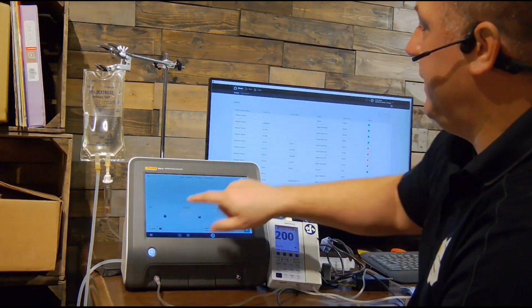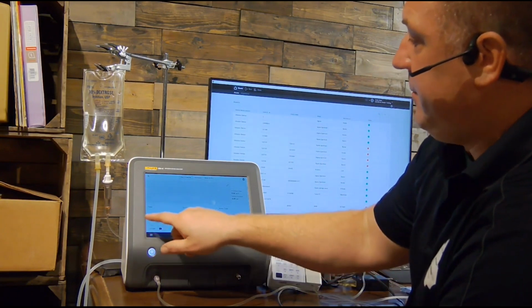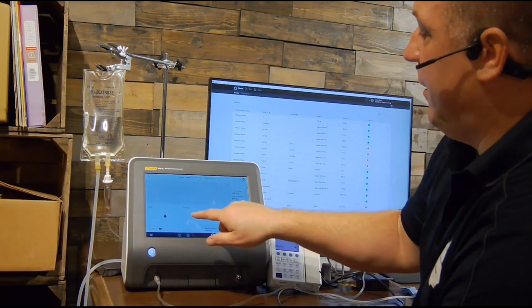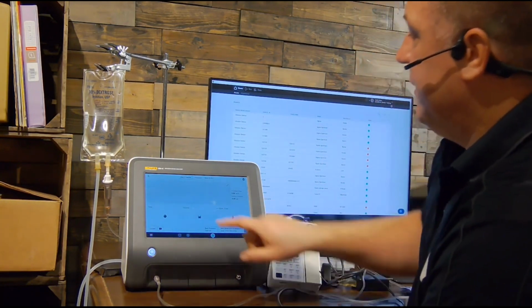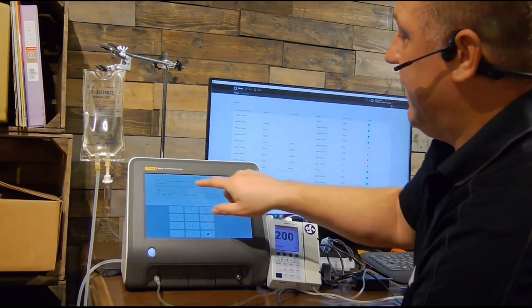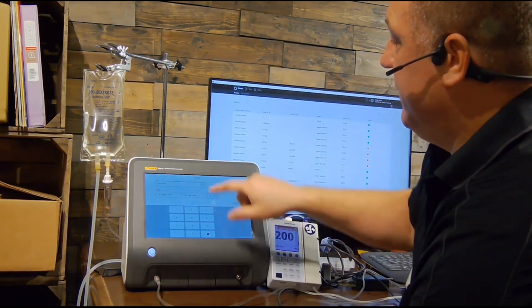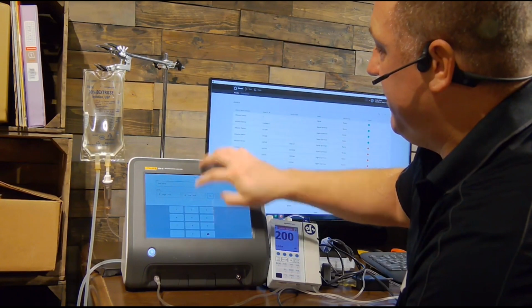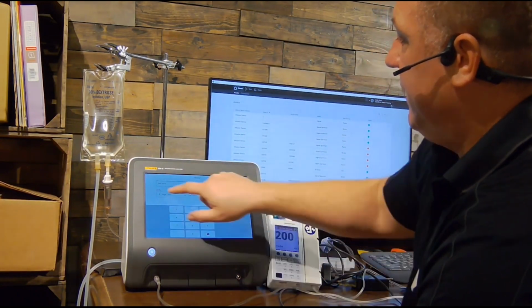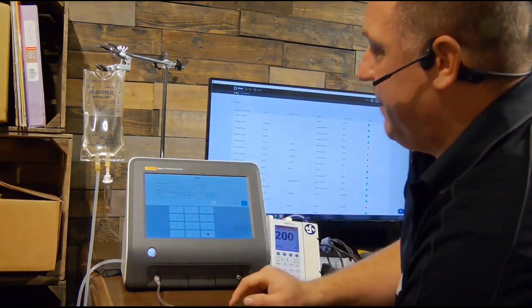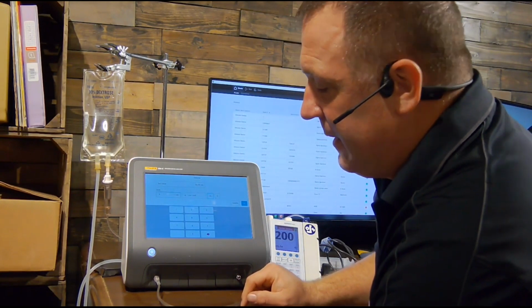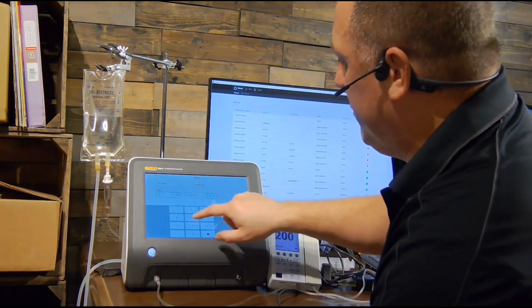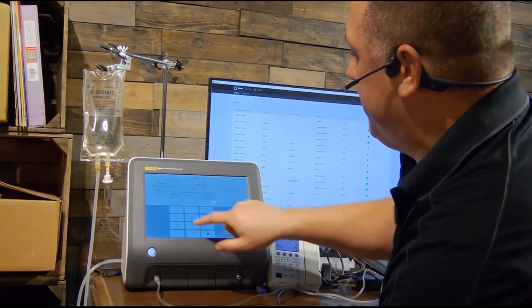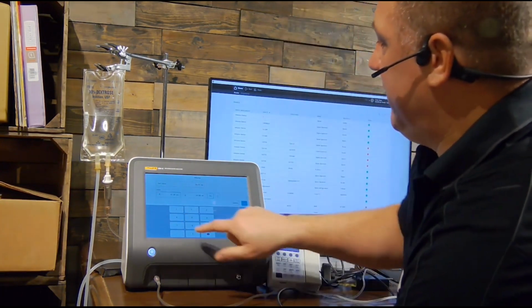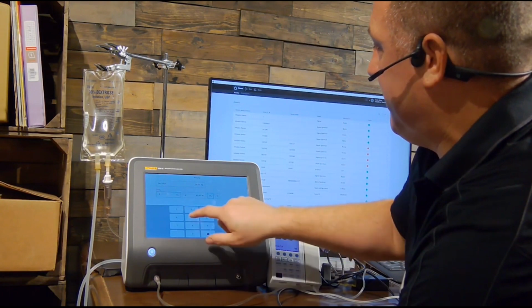Make that small again, and you have your time, your volume, and your mean flow. So if I go to my volume, or any of these, I could set my expected volume — in this case, maybe 50 milliliters. I can set my high limit, maybe 51, and my low at 49. Or some people read in percentages, so I could take this back, clear it out, and make it 5%.